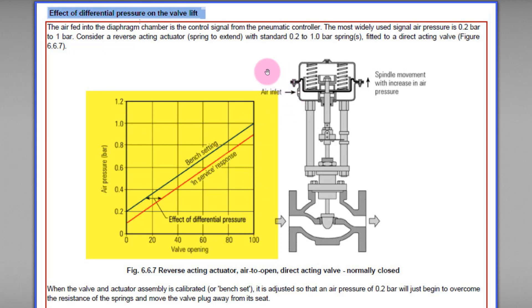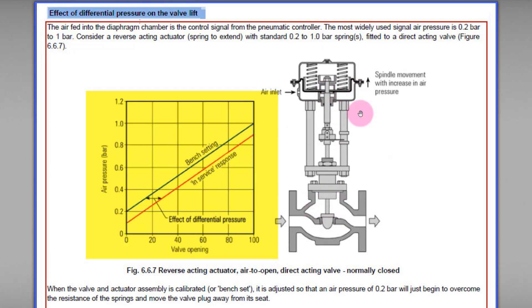When pressure reaches up to 1 bar or about 15 psi, the valve will be fully open. So if we apply the maximum pressure of 1 bar or 15 psi to the actuator, it pushes the actuator diaphragm to the maximum outward position, and the attached stems and valve plug move upward to fully open the valve.